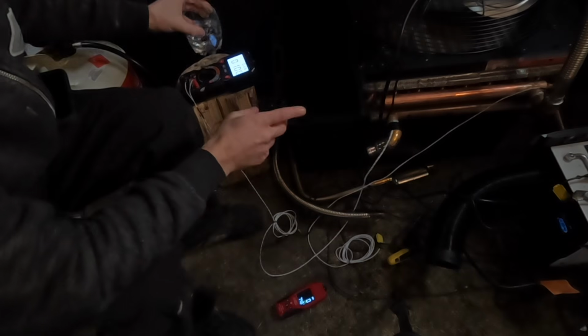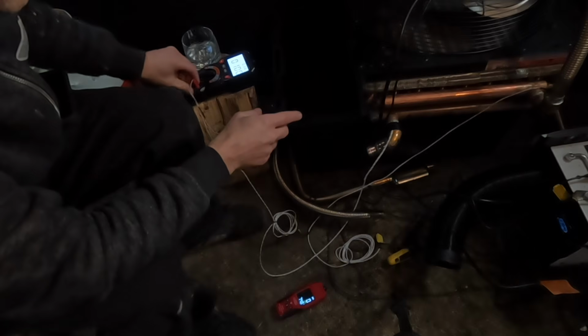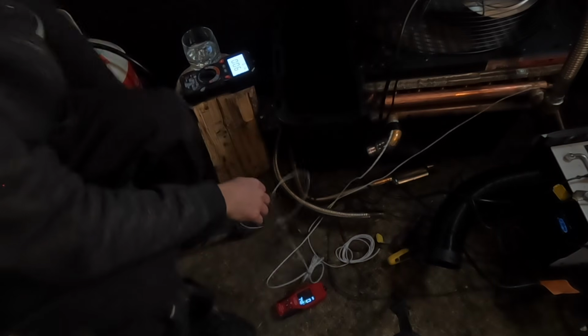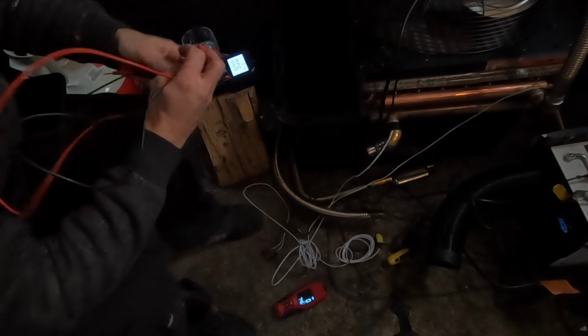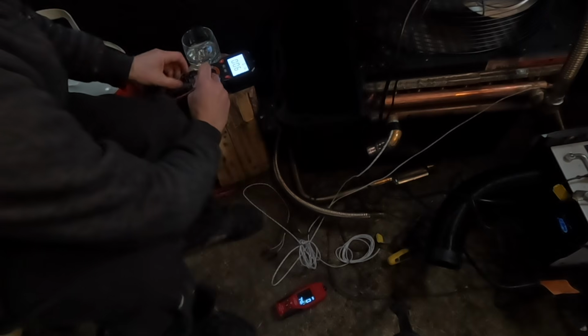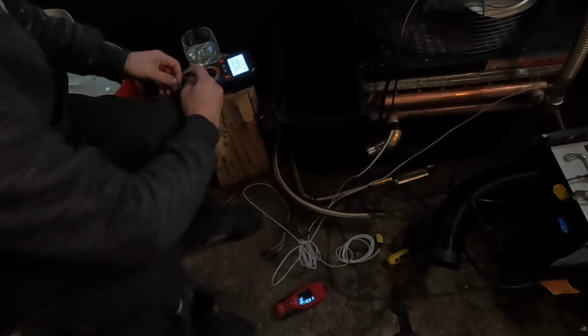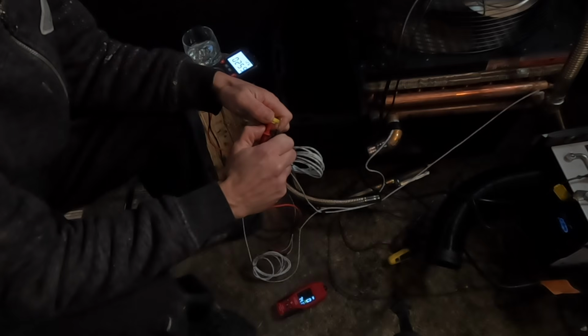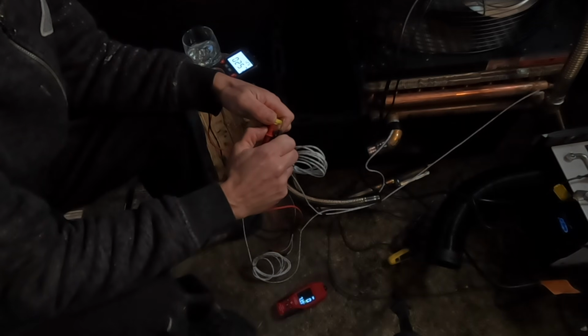So we're at 38 Celsius on the outlet. Now we're going to check the inlet, which is a bit clumsy because I have to plug in my leads to check the other sensor - I only have an actual plug on one. Inlet temperature to the heat exchanger is 259 Fahrenheit, or 126 Celsius.